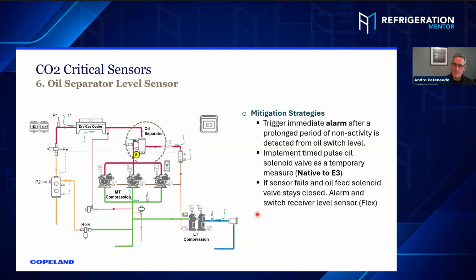Depending on whether they're using temperature to transfer the oil, or using pressure to transfer the oil, are they using optical eyes, are they using level sense? There is a lot to it. It's not like, oh, the compressor's low in oil, we'll just add oil. There's relays, switches, coils, a lot to it. So take your time to understand the system you're working on.